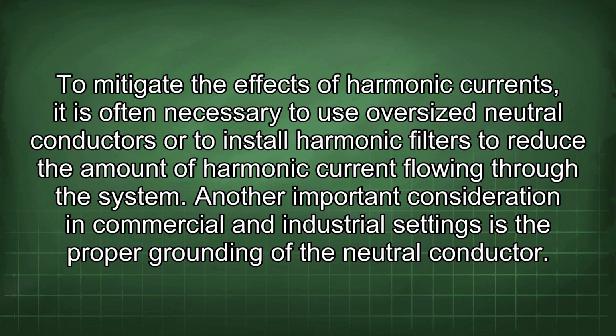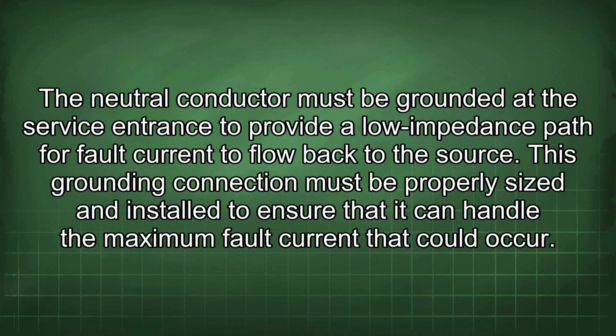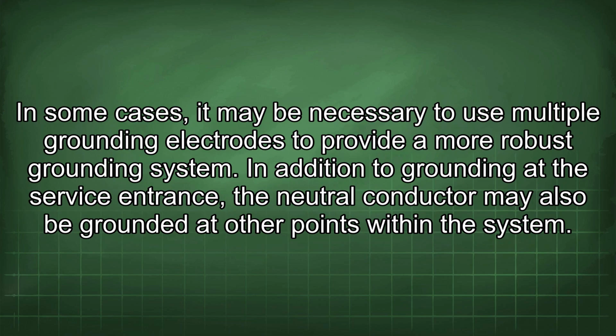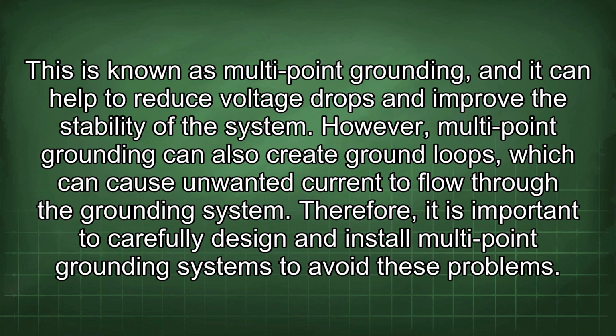Another important consideration in commercial and industrial settings is the proper grounding of the neutral conductor. The neutral conductor must be grounded at the service entrance to provide a low impedance path for fault current to flow back to the source. This grounding connection must be properly sized and installed to ensure that it can handle the maximum fault current that could occur. In some cases, it may be necessary to use multiple grounding electrodes to provide a more robust grounding system. In addition to grounding at the service entrance, the neutral conductor may also be grounded at other points within the system. This is known as multi-point grounding, and it can help to reduce voltage drops and improve the stability of the system.